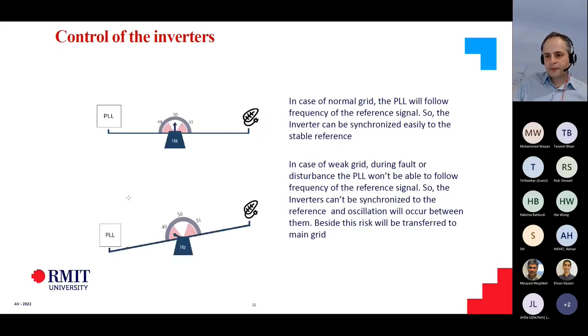Now, as I mentioned, if we have a very perfect grid with a very good reference signal, the PLL would perfectly work and we won't have any issue. But if we are dealing with a weak grid, that's not going to be the case, and the PLL may not be able to follow that reference. It will follow the reference signal, but we might have frequency oscillations, and that would create stability issues for the inverters themselves. That's something we really need to solve for future grids when we'll be dealing with a very weak grid, which doesn't have lots of voltage support from the synchronous machines.